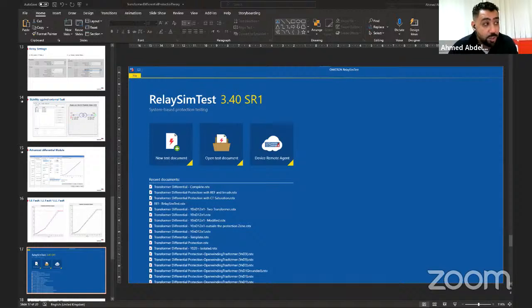What else can I do? I will go to test data, change any value here. For example, 10. And I have three faults with a different bias value, and I expect that the differential current will be 0. This is related to the stability. And I can go here, for example, for the operating characteristic. You will see here that I have a different bias equation, different bias value.